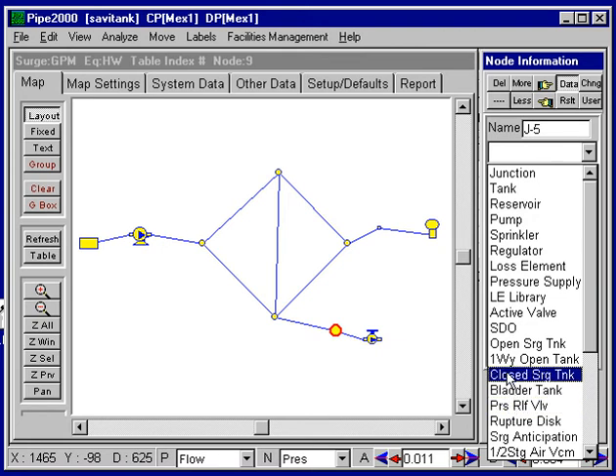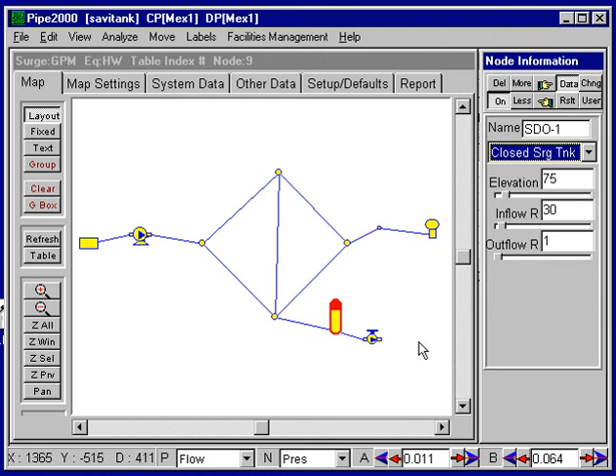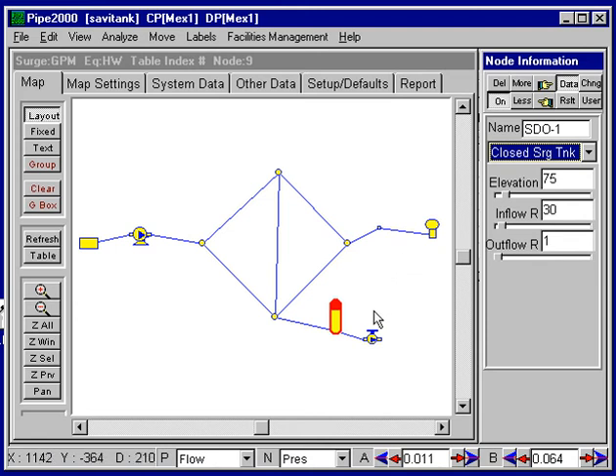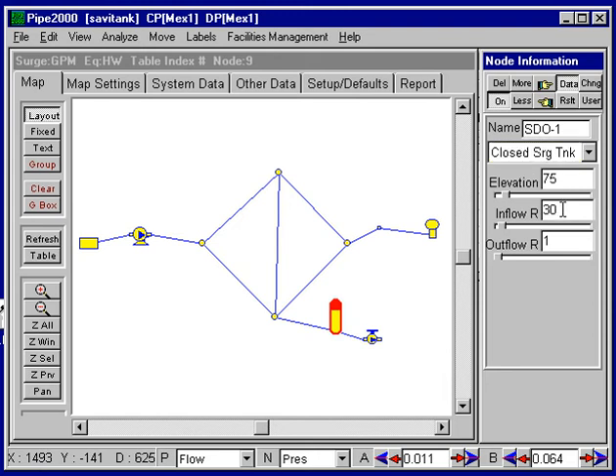For this illustration I'm going to choose a closed surge tank, which is a device that has gas in it and as the pressure goes up the gas becomes compressed. The data required will appear over here. First we need some resistances in and out, and I'll just use the number one, which means there will be a one foot head drop for a flow of one cubic foot per second.